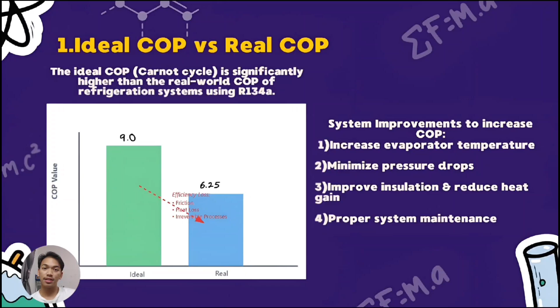Our research identifies 4 key system improvements that can significantly boost real-world COP closer to theoretical values. First, increasing the evaporator temperature. By operating at a higher temperature, we reduce the compressor work required, directly improving the COP. Second, minimizing pressure drop throughout the system. Every pressure drop in components represents wasted energy that reduces overall efficiency. Third, improving insulation and reducing heat gain. Better insulation means less cooling load, which translates to lower energy consumption and improved system performance. And finally, proper system maintenance. Regular maintenance ensures components operate at peak efficiency throughout the system lifetime. A poorly maintained system can lose 20 to 30% of its efficiency.